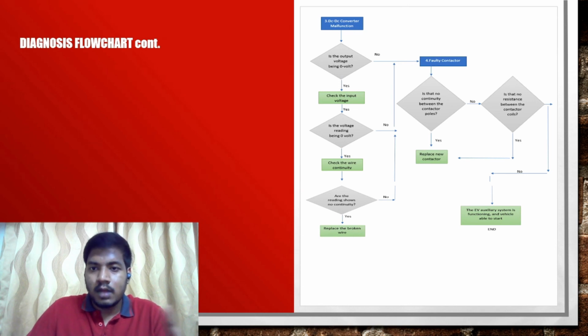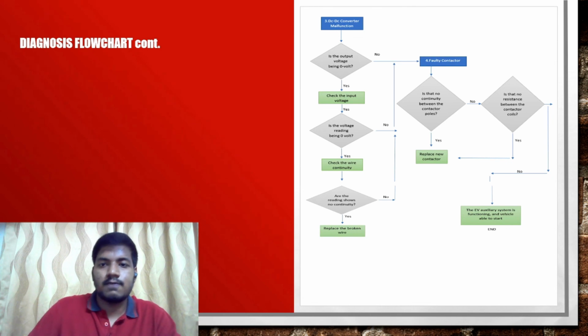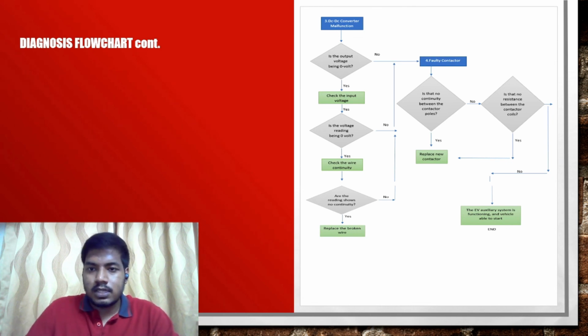Then we go to the fourth possible cause, which is a faulty contactor. We ask: is there no continuity between the contactor poles? A good contactor should have continuity between the contactor poles. If there is no continuity between poles, then we should replace the contactor.